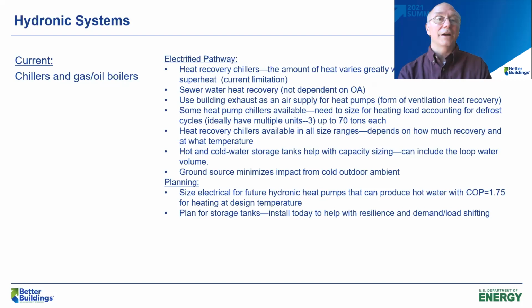There are other strategies too, like water-to-water systems. A lot of energy is tied up in sewer heat recovery — you already paid money to heat that water. There are systems out there for sewer heat recovery that take that heat and dump it into the building's heating system. Several buildings now use this exclusively for heating. They also combine nicely with heat recovery chillers, where the chiller acts as preheat and the sewer heat recovery finishes raising the water to a higher temperature.